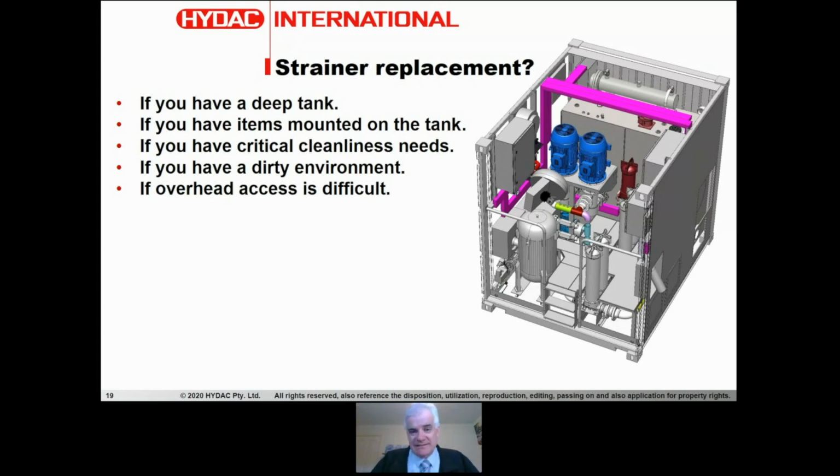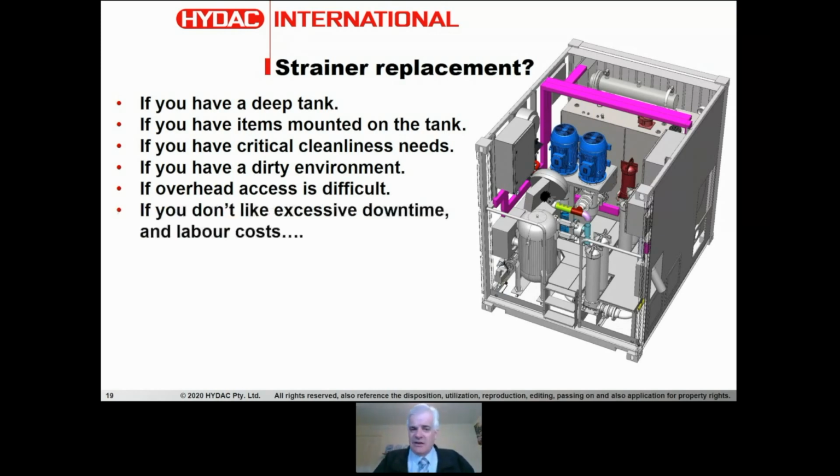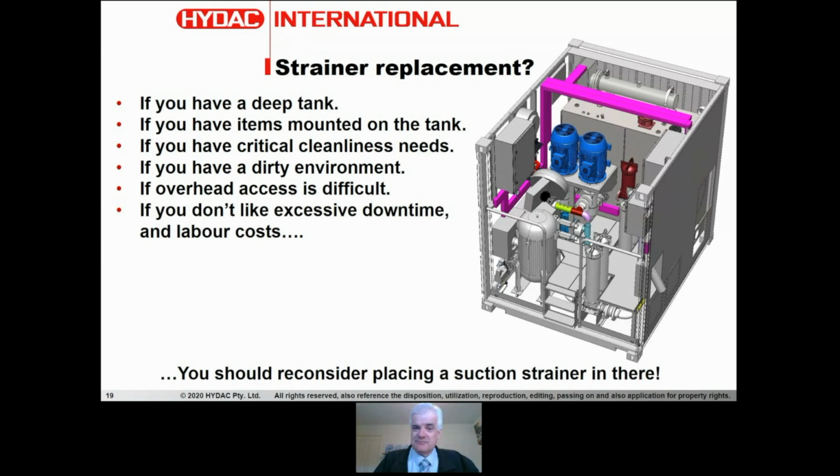If overhead access is difficult, sometimes, for example, you might have heavy items, manifold blocks and things on the tank. If you don't have overhead access where you can get a crane in there and do it safely, you don't want to be opening that lid up. So if you don't like excessive downtime and excessive labor costs and really just difficult jobs, then you should reconsider placing a suction strainer in that reservoir. Okay, there's really other ways you can do your filtration more effectively. So yes, there's advantages to suction filtration, but there's also disadvantages, and you can see in the application of it, you can make some bad decisions.